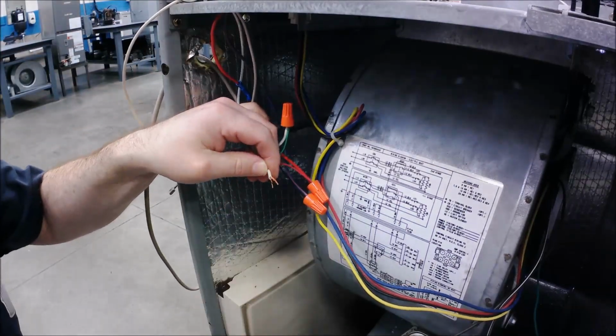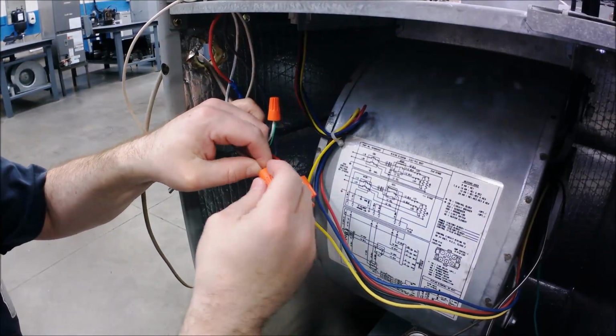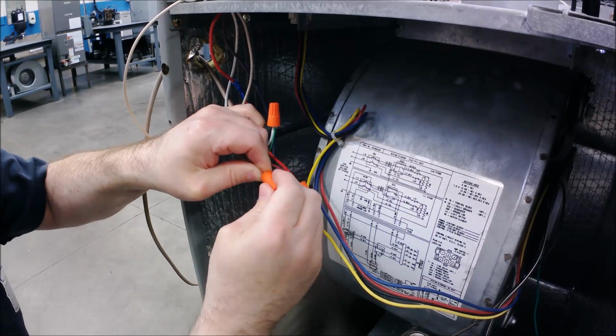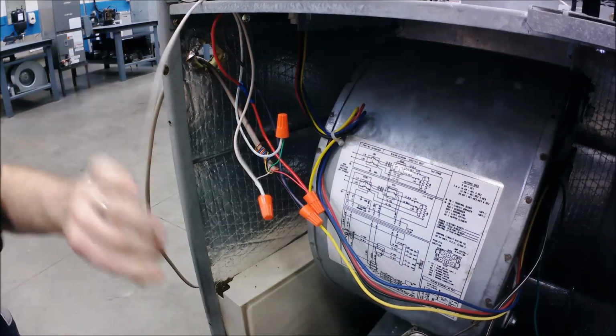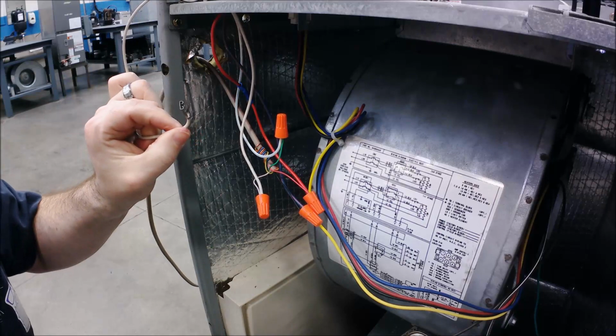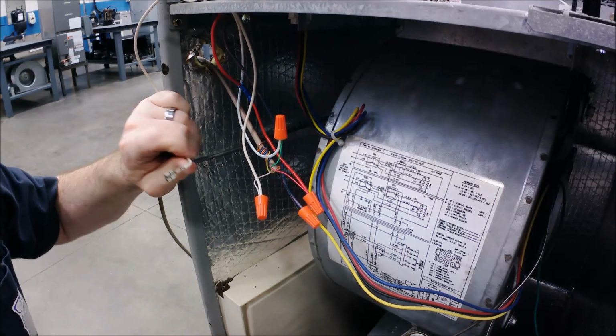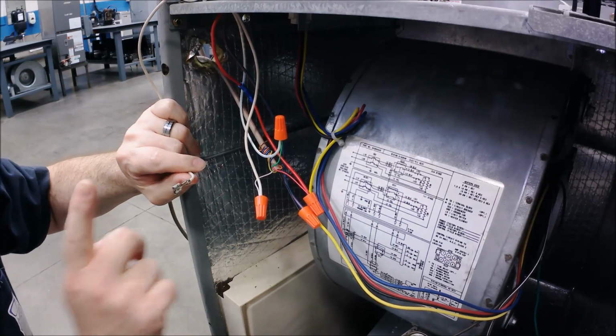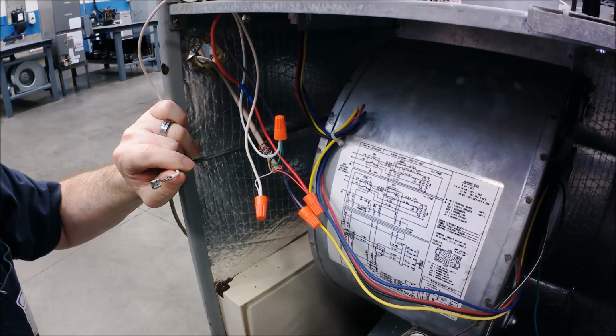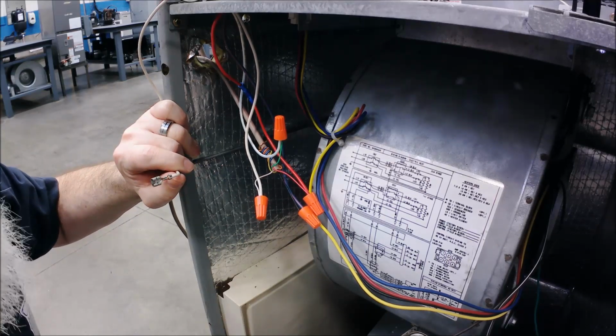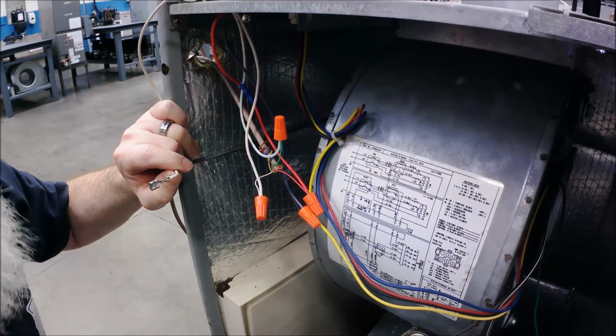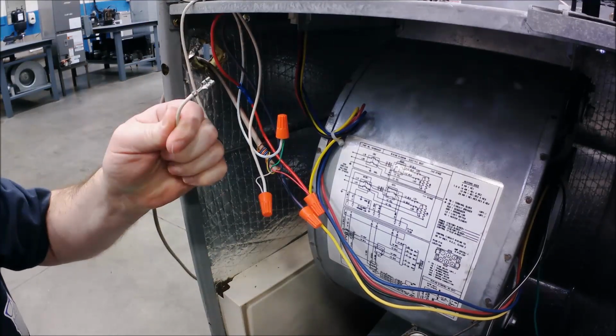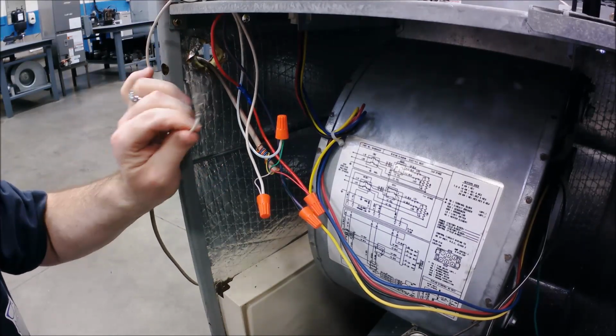So white to white. Pretty much everybody watching this video probably knows that, but if you think about it, where does the other end of this white go? No matter what safeties it goes through, limits or whatnot, this has to go ultimately to your heat relay, your heat sequencer, heat contactor, or whatever you use to turn it on. If it was a gas furnace, it's ultimately going to the gas valve.